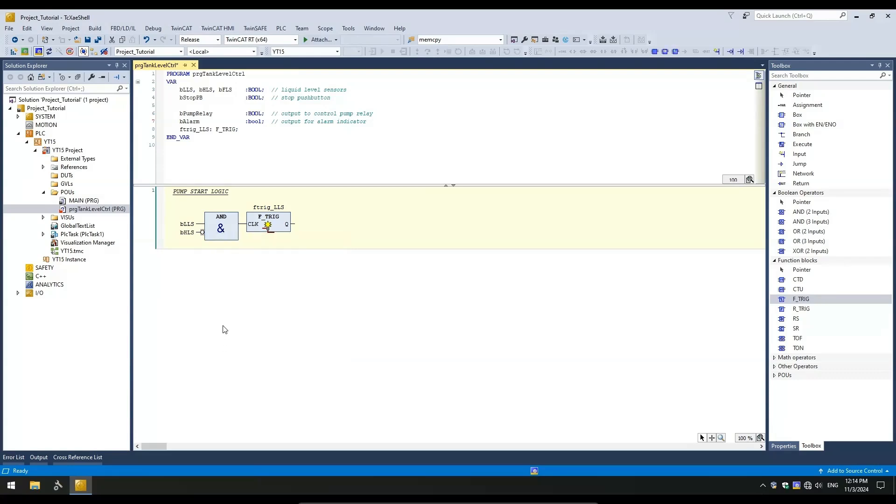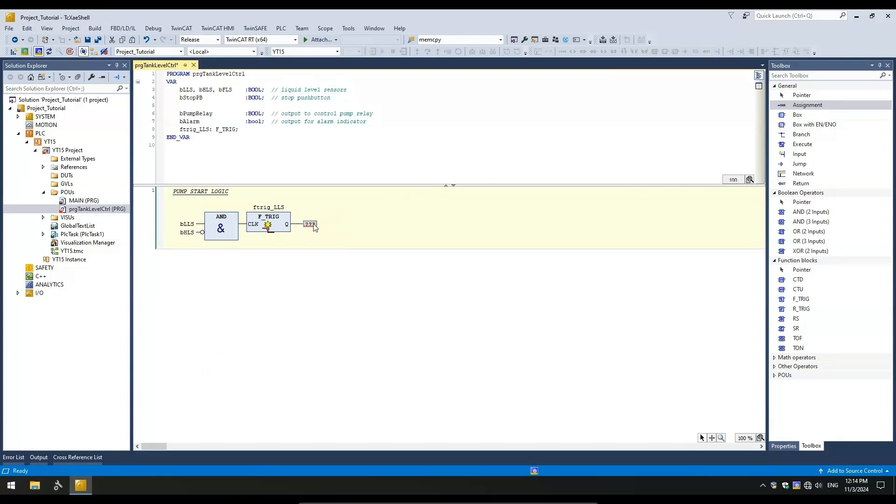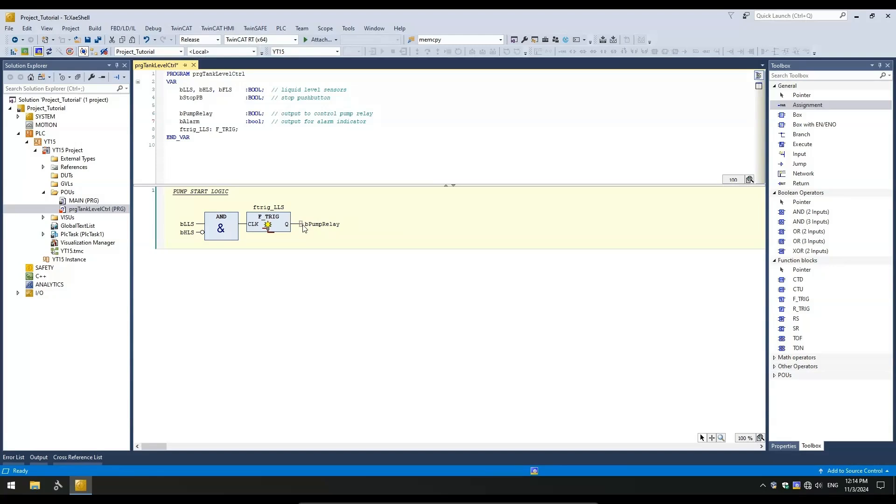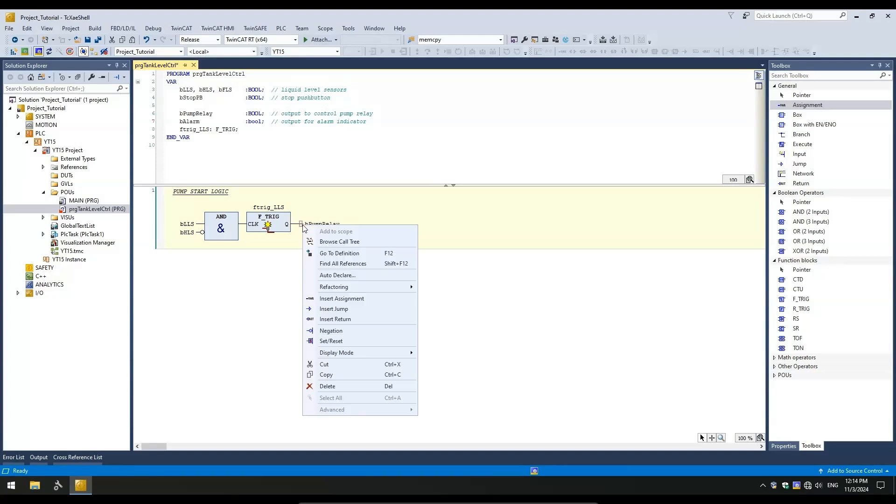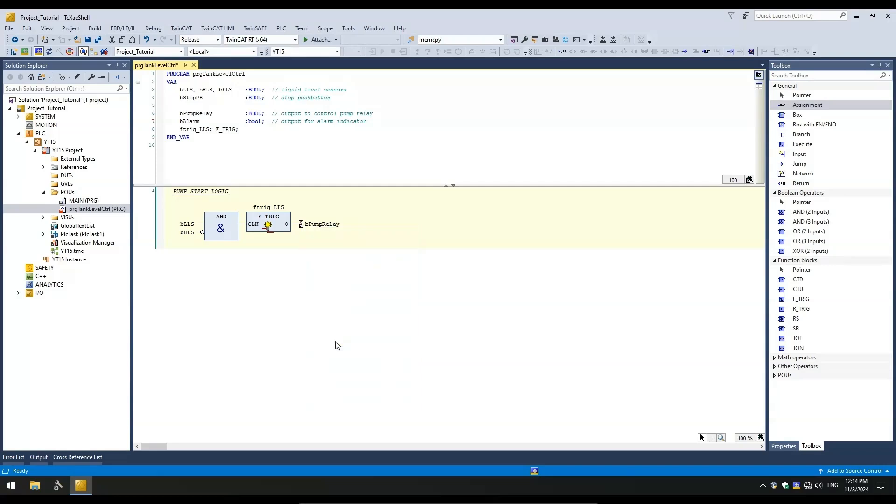Finally, let's assign the pump relay output to the falling edge trigger's output pin. Simply add an assignment pin from the toolbox and enter the variable name to it. We want this output to stay latched. For this, we can right-click and use the set option. This will be indicated by the letter S next to the variable name on the output pin. The pump start logic is done. A falling edge on a low-level signal and no signal on high-level sensor will set the pump relay on.